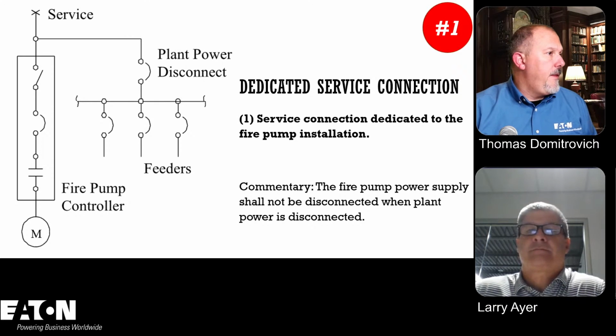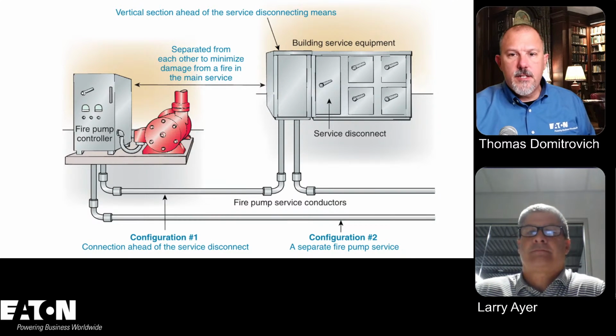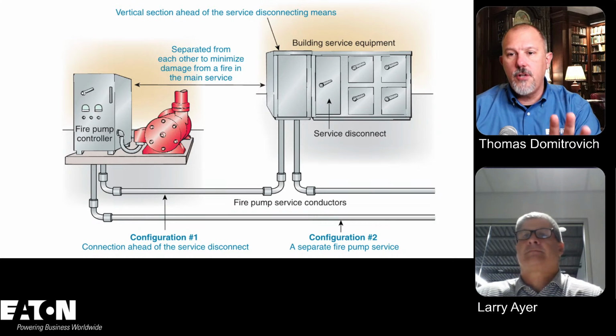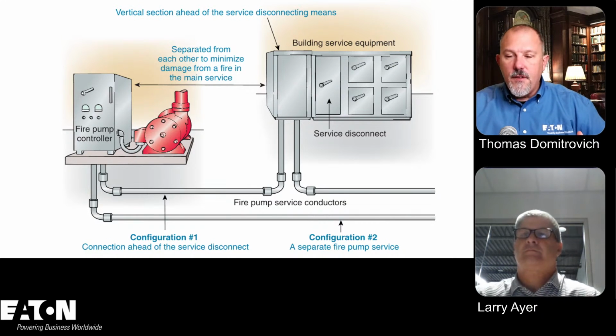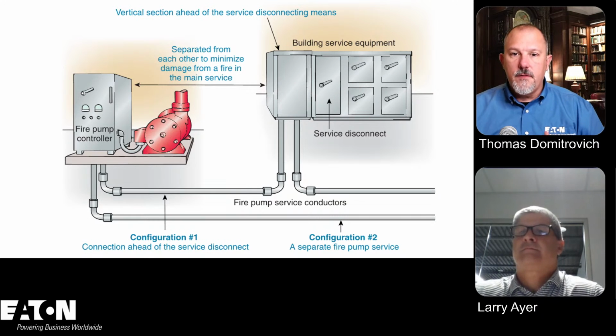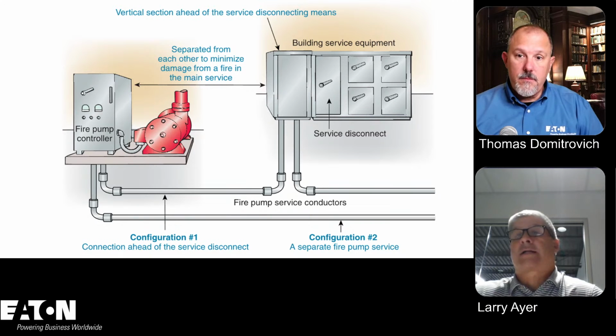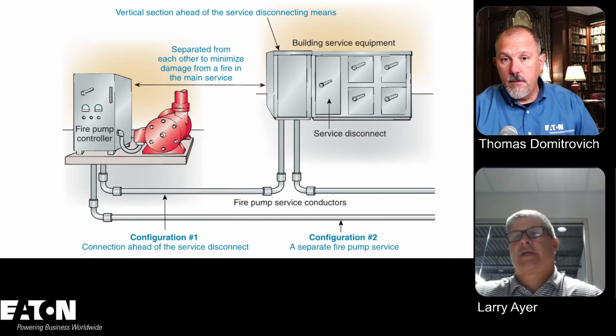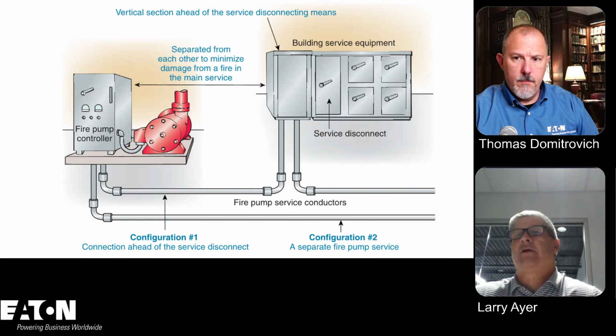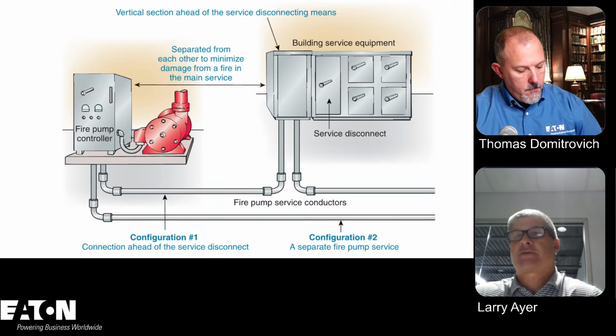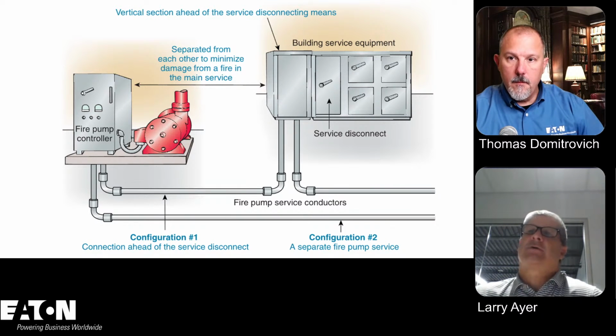Yep. And I think this next slide was nice because it shows that you're coming off of the line side of your service disconnect, not the load side. That's a critical point, right? Correct. And the takeaway from this is looking at 2 different things here. One, you see that the fire pump service conductors come in from the service from the utility company. They go into that first cabinet, and once they go into that first cabinet, then they come back out of that cabinet.